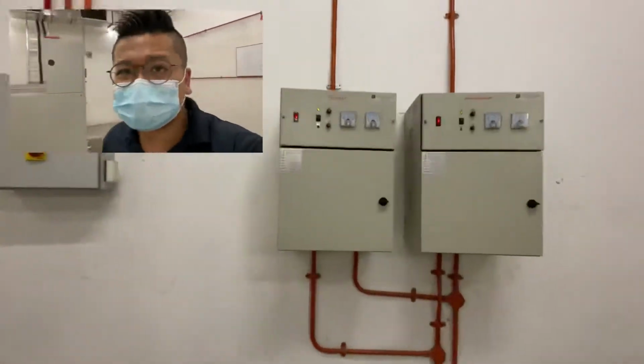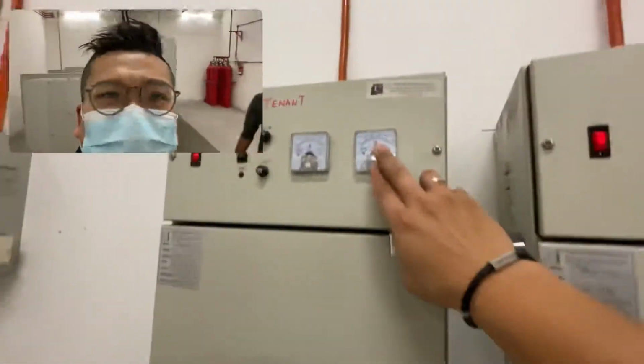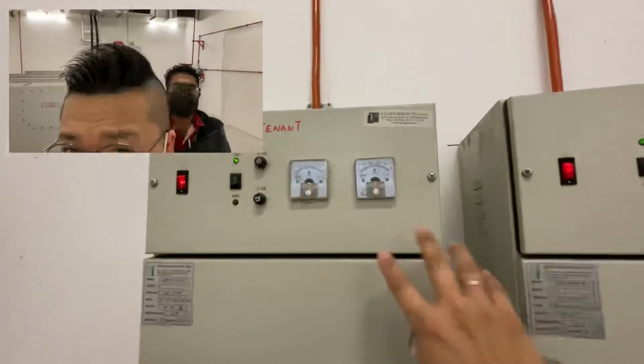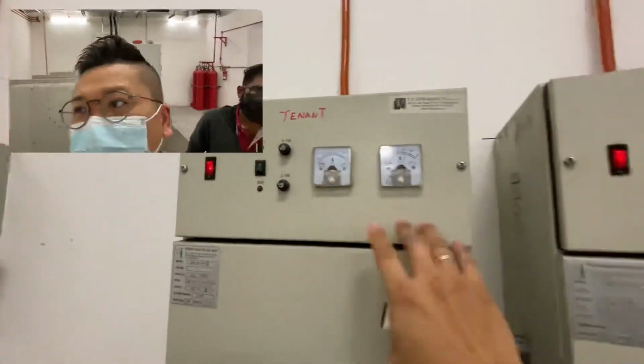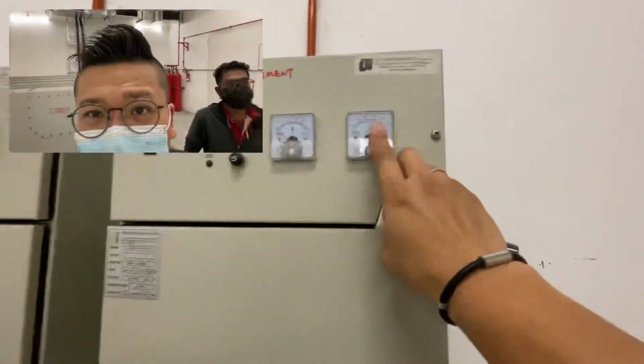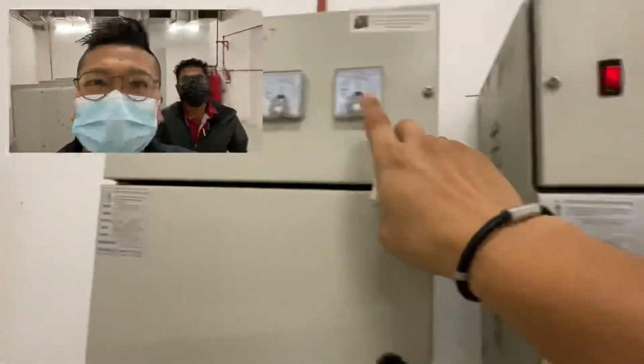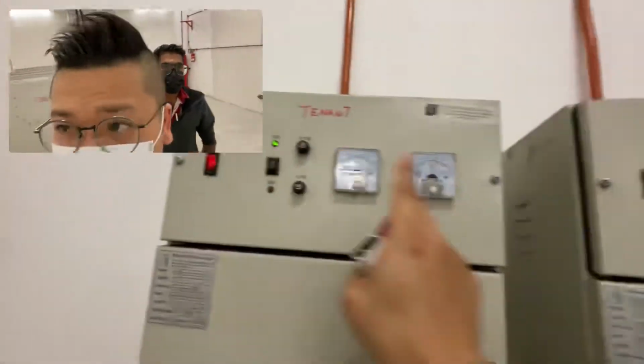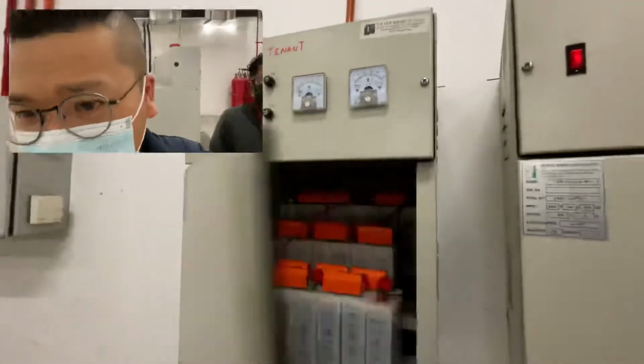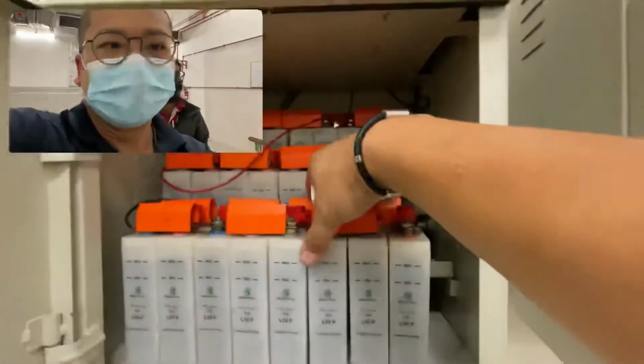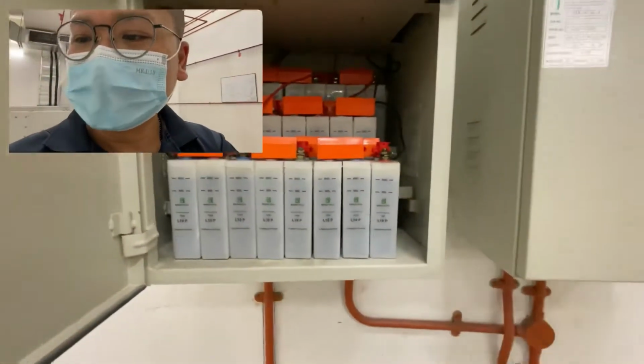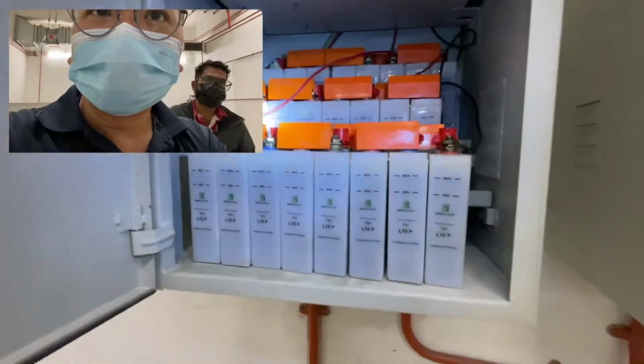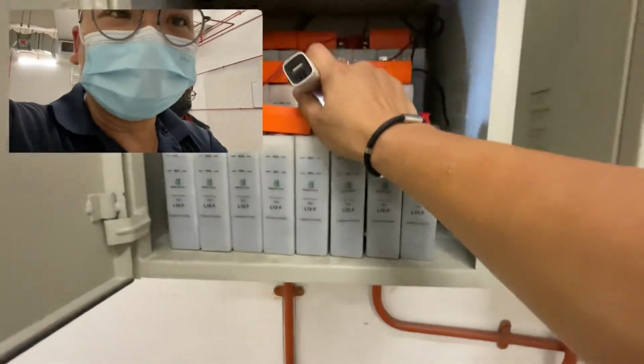First of all, we need to check the tripping unit. Okay, we have two tripping units here. One is for the tenant switchgear, another one is for the management switchgear. The voltage is above 30 volt. Above 30 volt, the charger is operating. Let's check the battery. Okay. Termination all okay. Battery water sufficient. No overcharging.